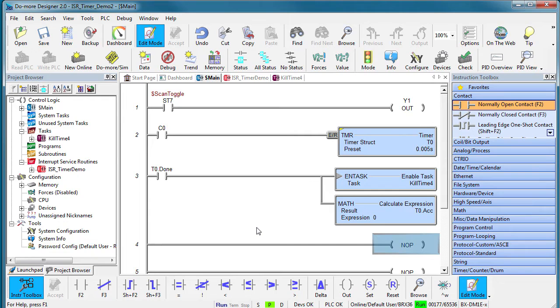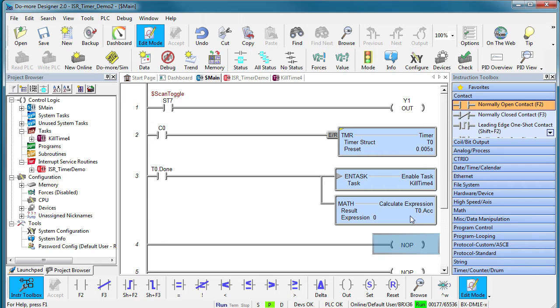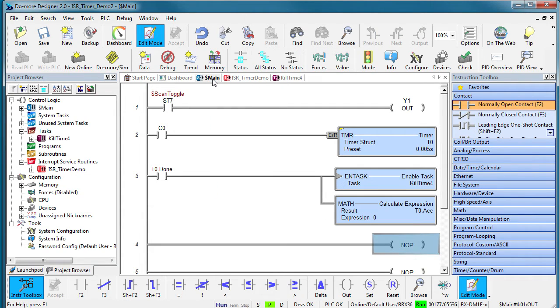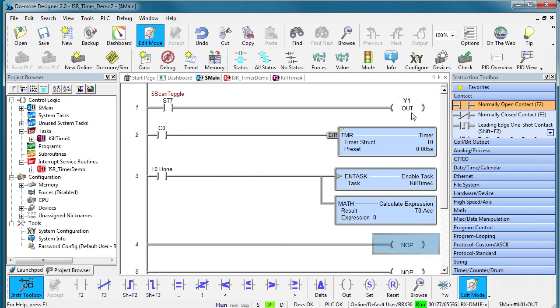I've created a little ladder program that uses a timer to enable a task every millisecond and also resets the timer's accumulator so it will start counting up again to 1 millisecond. The task just increments a register a thousand times to waste some scan time. I am also toggling Y1 each scan using this scan toggle bit which inverts every scan. That will get updated at the bottom of the scan just like all other normal outputs.